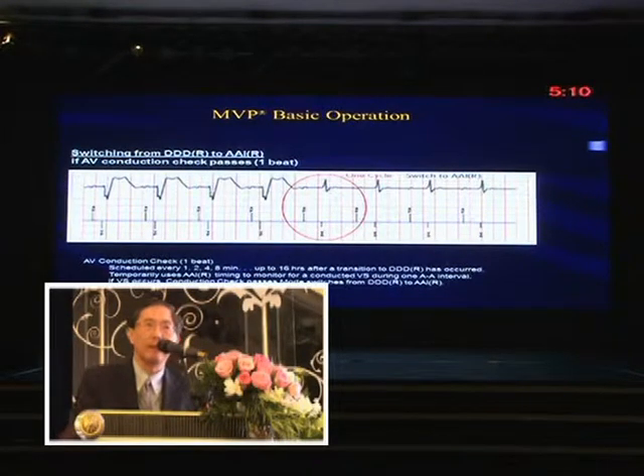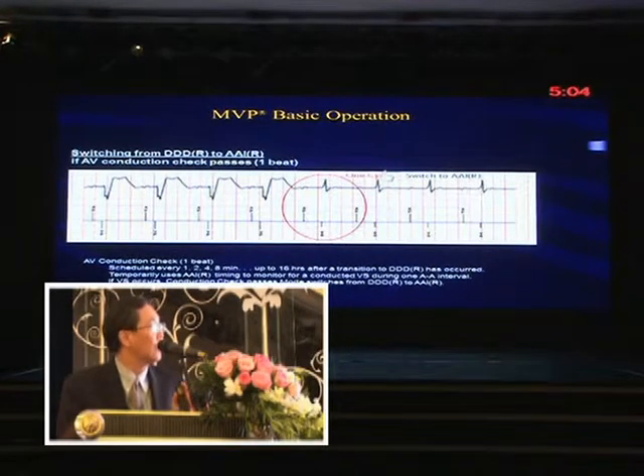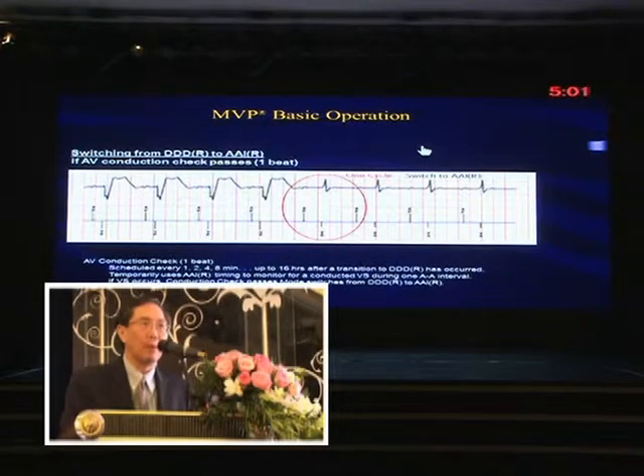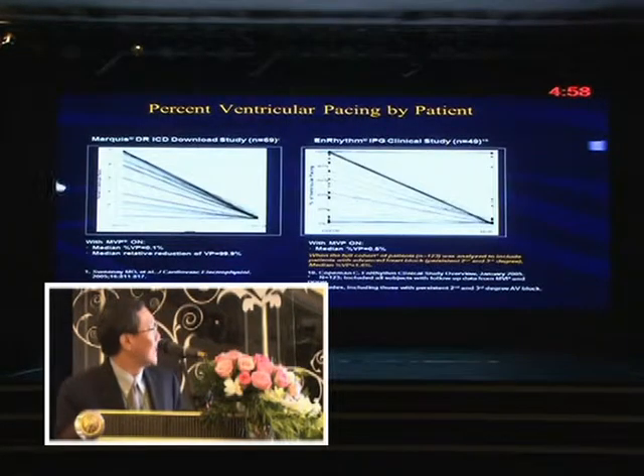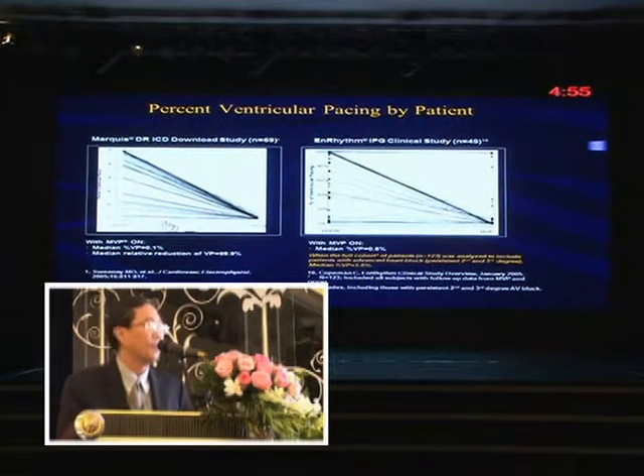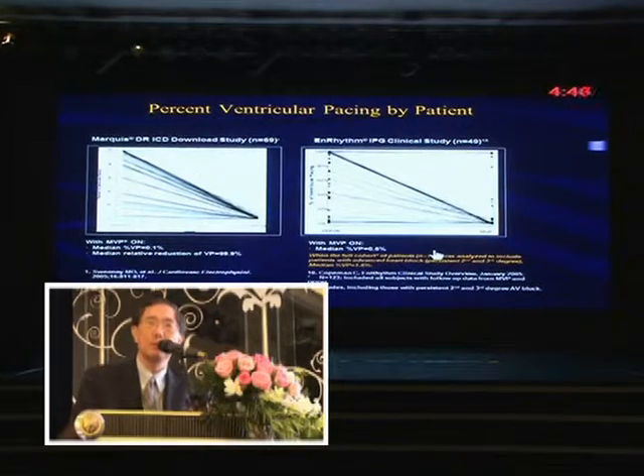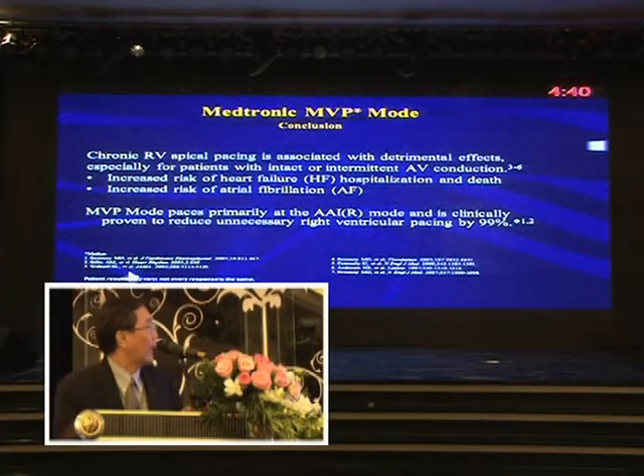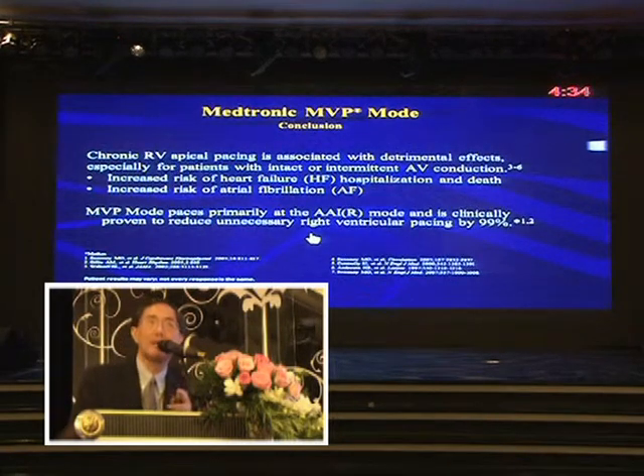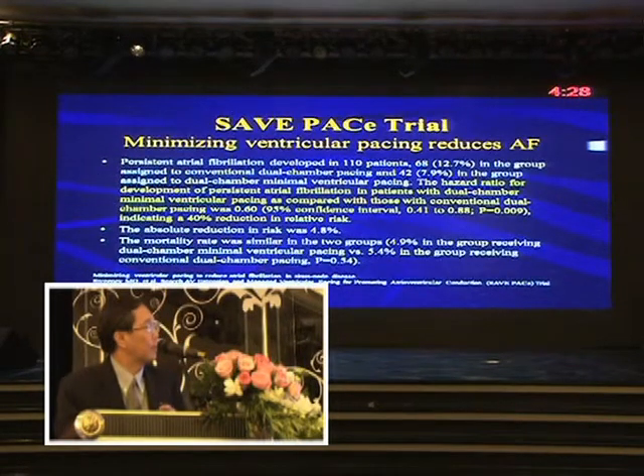So it's quite a smart device. I emphasize, for a normal heart, this will be an excellent idea to keep you in an AAIR mode without worrying. At most, you have a slight gap most of the time. Using this algorithm, they found that ventricular pacing has dramatically gone down to the region of 0.1 to 2%. So yes, you still can pace the ventricle, and you still must pace the ventricle when the ventricle is too slow. The thing is, it has reduced the unnecessary RV pacing by as much as 99%. So a very effective algorithm.